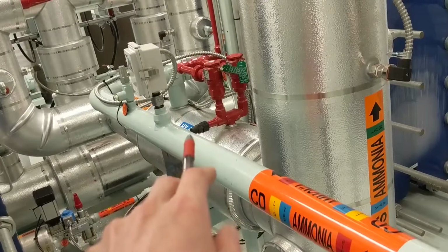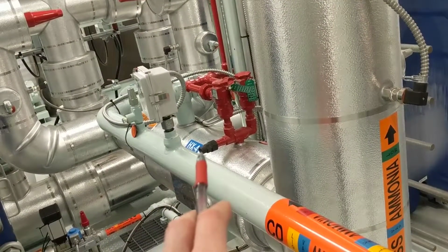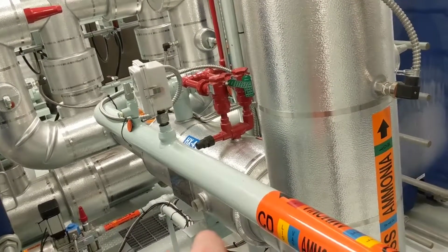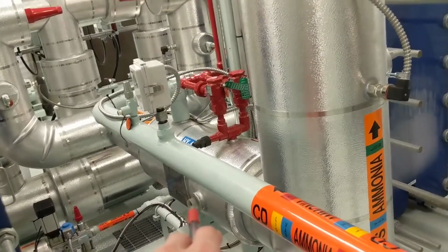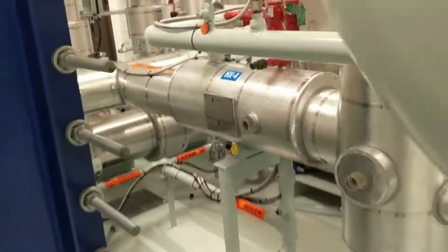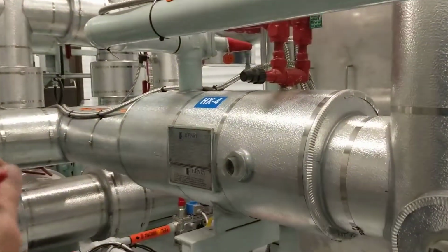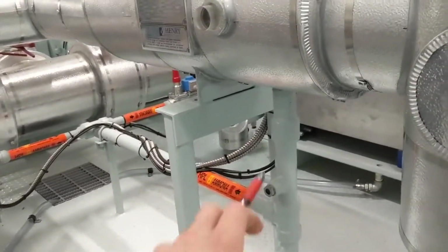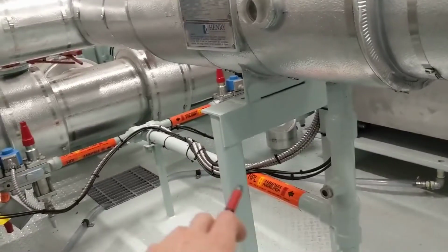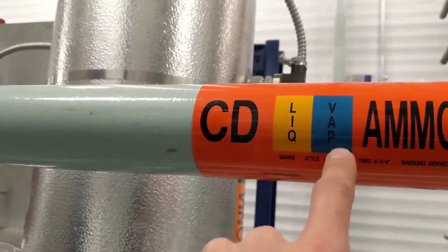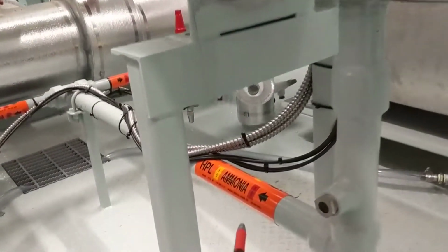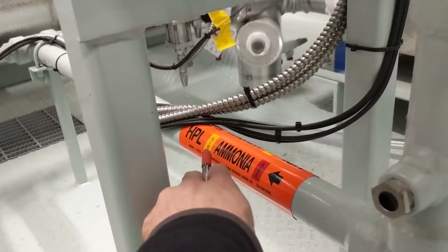This is flowing over here to HX4. So HX4, that heat exchanger, is an ammonia heat exchanger, and it effectively acts as a subcooler. So that's getting your ammonia to definitely be in a liquid state by the time it comes down out of the heat exchanger and flowing through here. So you can see here we had liquid and vapor. After it passes through this heat exchanger subcooler, you'll see it's only flowing out here as a liquid only.